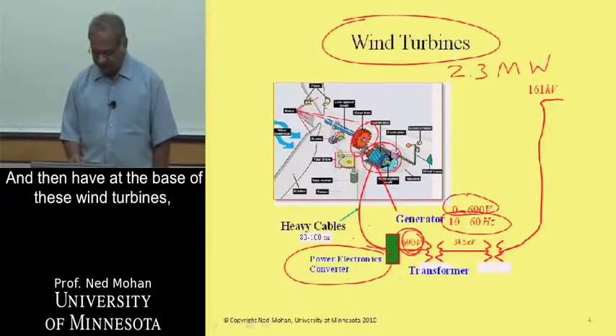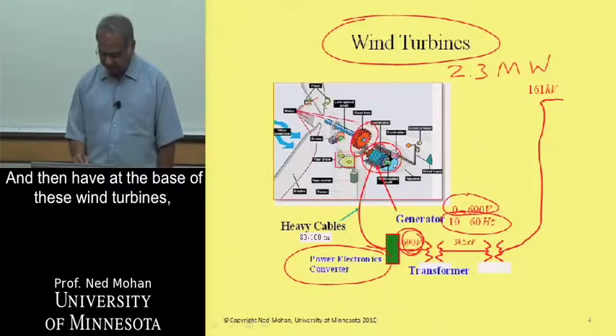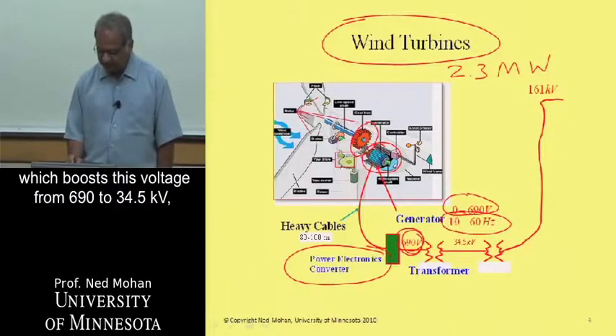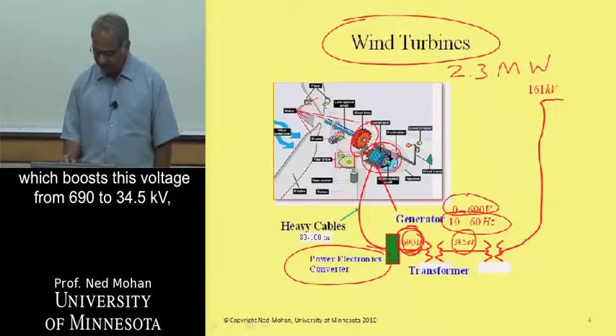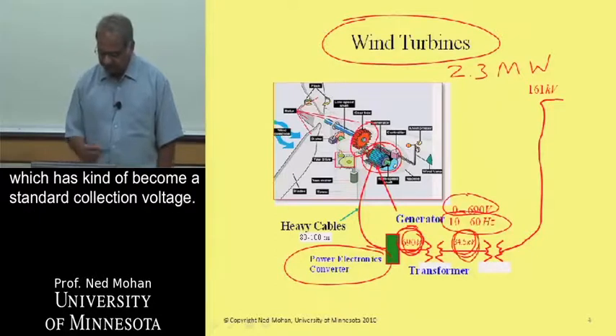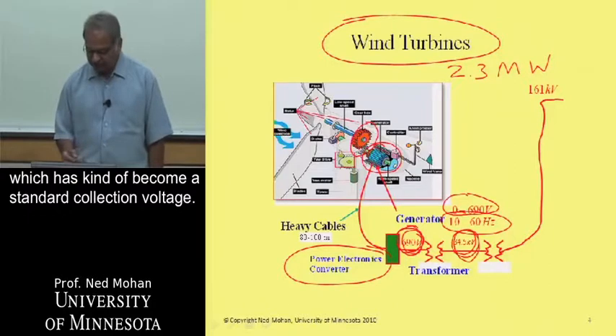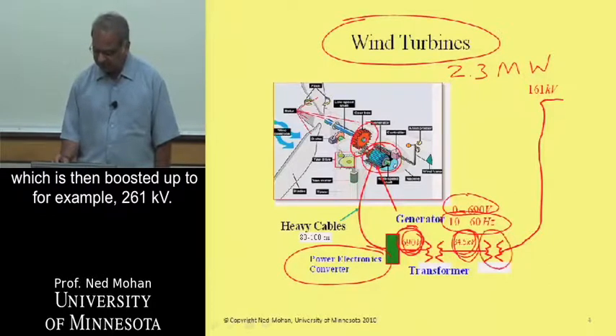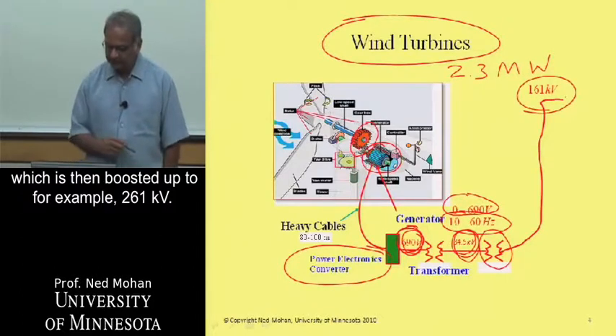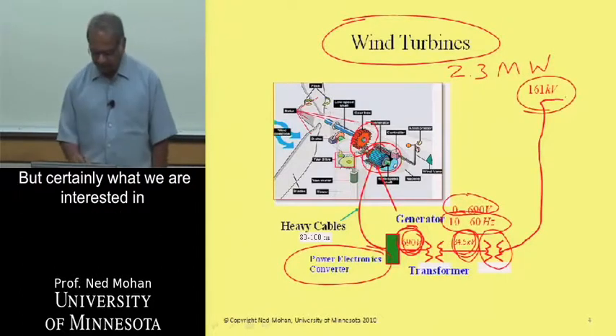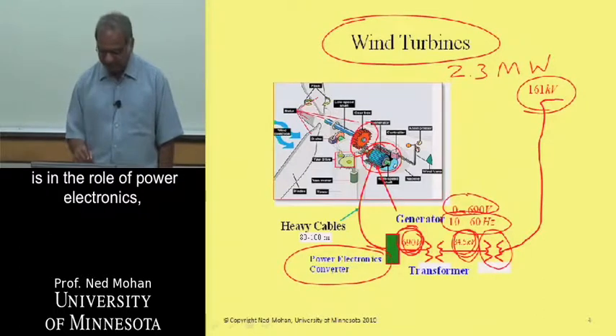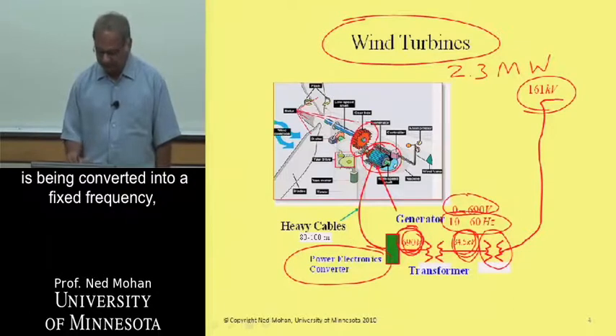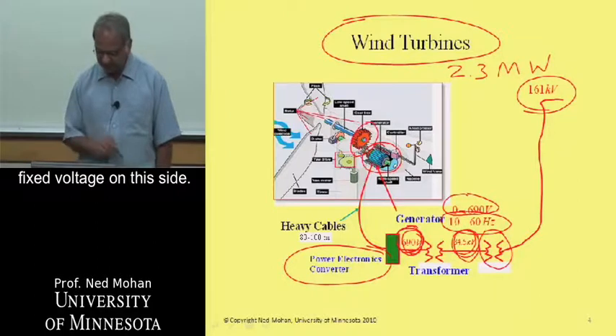At the base of these wind turbines, there is usually a transformer which boosts the voltage from 690 volts to 34.5 kV, which has become a standard collection voltage. Many wind turbines are connected to this collection voltage, which is then boosted up to, for example, 161 kV. What we are interested in is the role of power electronics, where variable frequency, variable voltage is being converted into fixed frequency, fixed voltage on the output side.